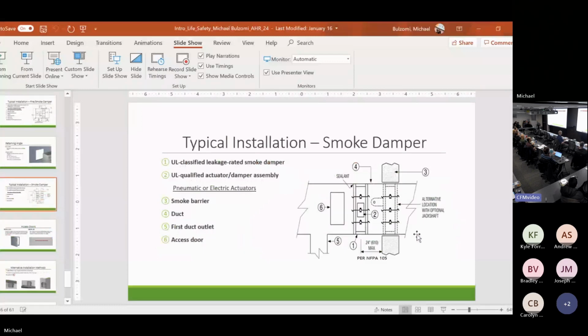So smoke dampers, since they're not fire rated and they're not structurally required to stay within the partition like a fire damper is, I can install a smoke damper up to 2 feet outside the partition. There's no additional testing for an out of wall smoke damper. It's the preferred installation. Contractor will cut a hole in the duct, slip his smoke damper in, seal around it, call it a day. If you are specifying sleeves and angles on smoke dampers, take that out of your spec.